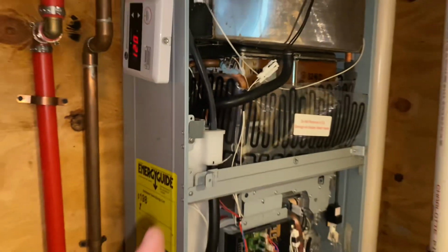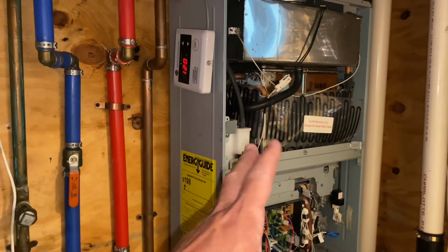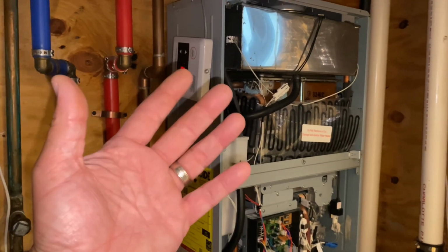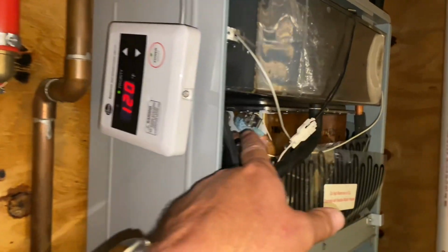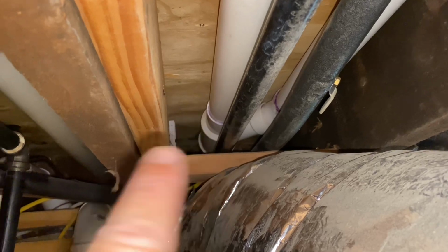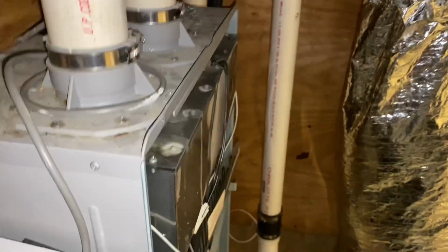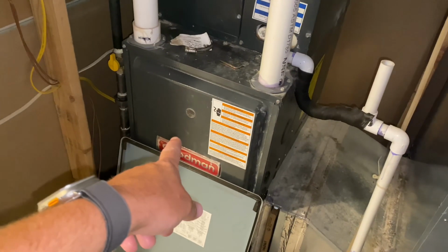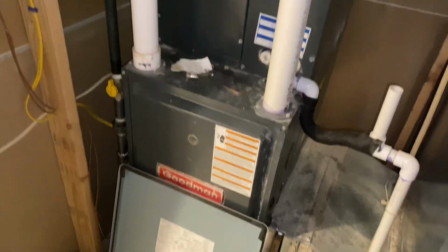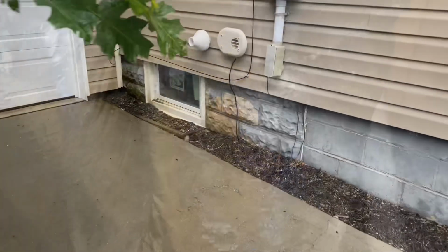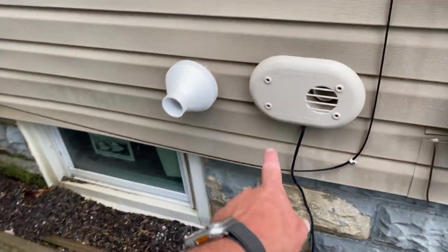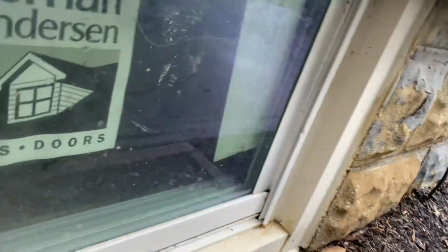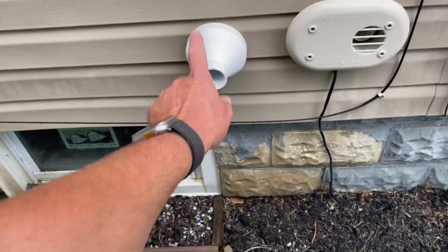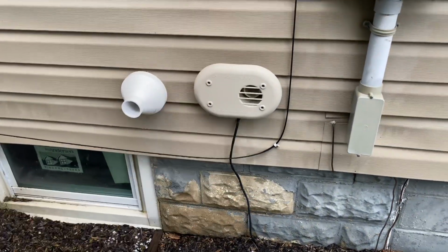So I called Rheem. We did a visual FaceTime call with an app that they were using. They wanted to see that, and then we also took a look at the exhaust piping outside. There's our concentric vent kit, and there's inlet and outlet for the tankless, which is right here. Follow this concentric vent kit, and that's going to our sealed combustion 90+% efficient Goodman gas-fired furnace. I'll show you outside in a minute. All right, here is the venting concentric for our furnace. The water heater is right there. So that's the furnace, and that's the tankless water heater. And this was totally acceptable to Rheem.